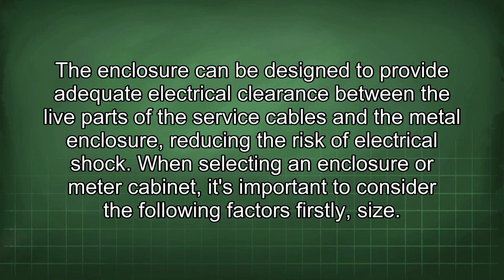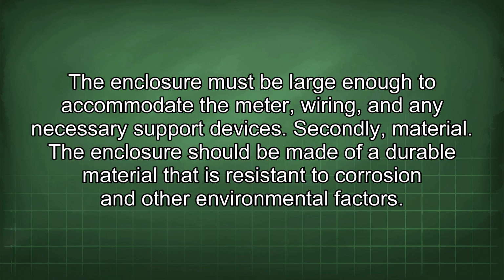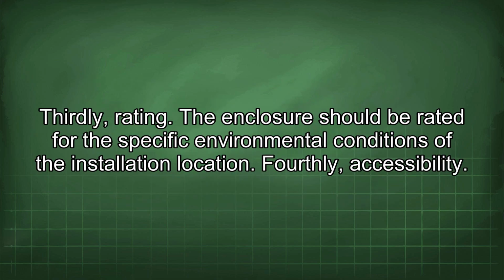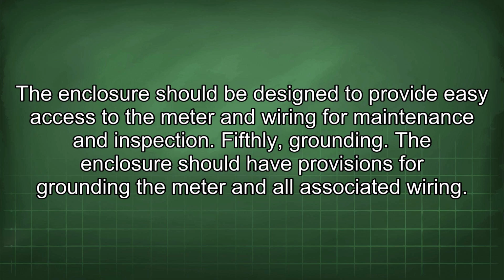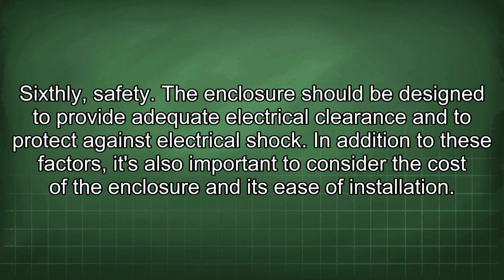When selecting an enclosure or meter cabinet, it's important to consider the following factors. Firstly, size. The enclosure must be large enough to accommodate the meter, wiring, and any necessary support devices. Secondly, material. The enclosure should be made of a durable material that is resistant to corrosion and other environmental factors. Thirdly, rating. The enclosure should be rated for the specific environmental conditions of the installation location. Fourthly, accessibility. The enclosure should be designed to provide easy access to the meter and wiring for maintenance and inspection. Fifthly, grounding. The enclosure should have provisions for grounding the meter and all associated wiring. Sixthly, safety. The enclosure should be designed to provide adequate electrical clearance and to protect against electrical shock.